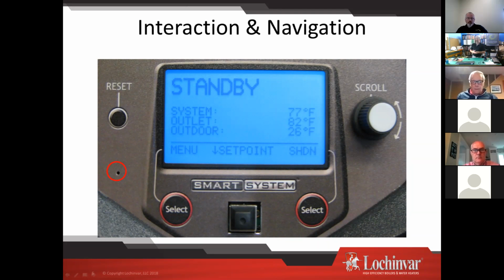Where does that come in handy? Well, let's say that Tommy calls me up and says, hey, my boiler makes noise at 37%. When I go out there and I want to see what he's doing, I could put it in service mode and dial that knob to 37%, and we could go and look. We could take combustion at 37%. We could hear what it's doing. There's a lot of things that we could do by adjusting it.